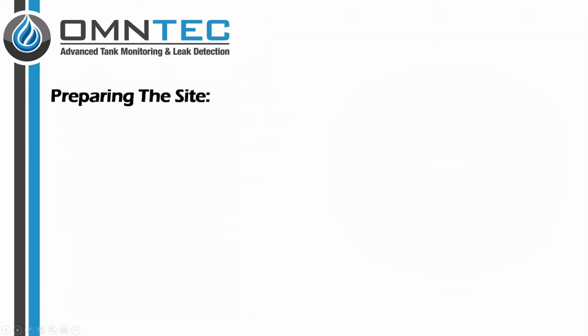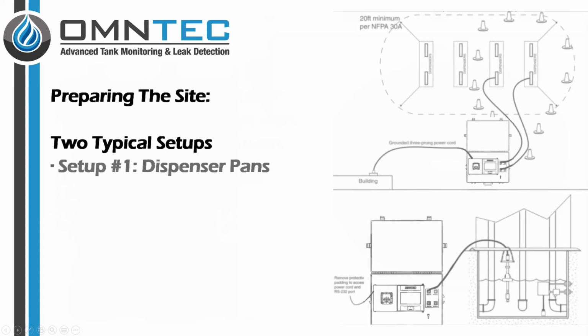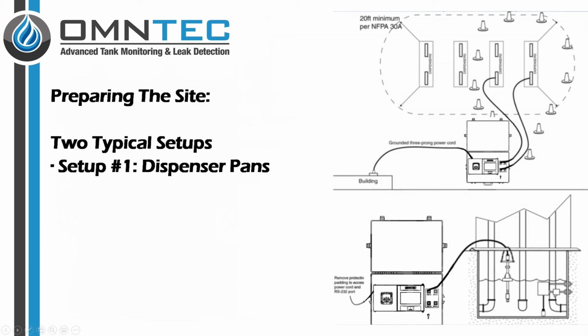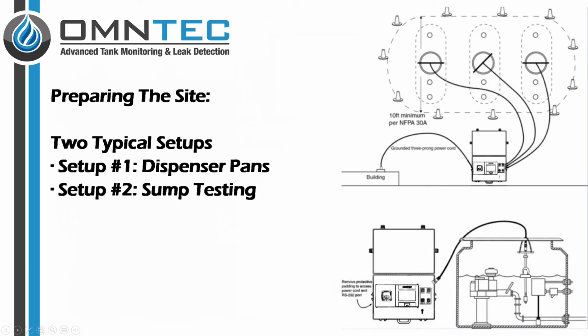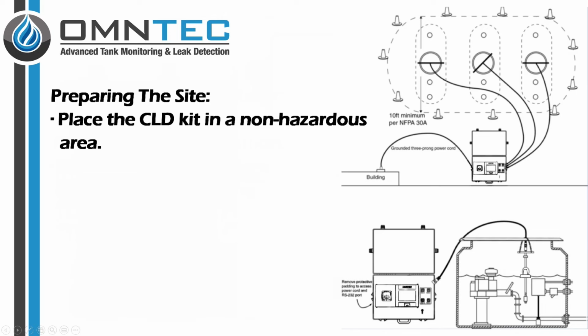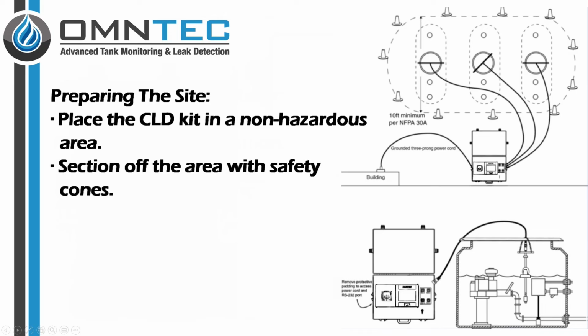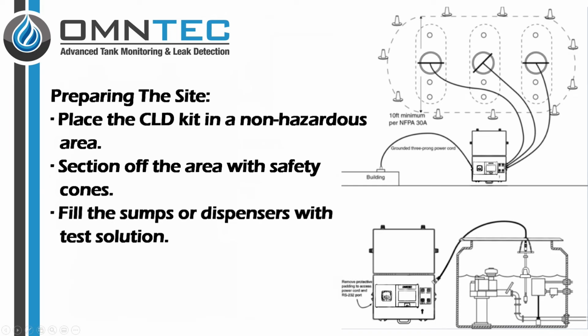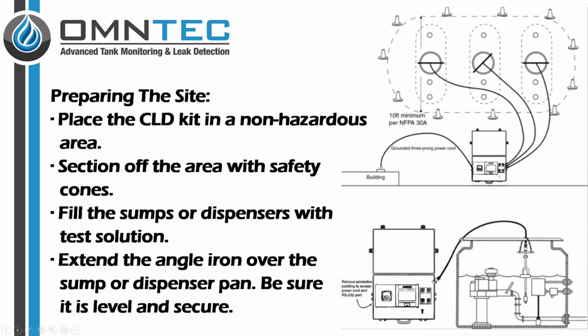Now, let's talk about preparing the site. There are 2 typical setups, one being for dispenser pans and the other for sump testing. Place the CLD kit in a non-hazardous area. Section off the work area with safety cones. Fill the sumps or dispensers with test solution. Extend an angle iron over the sump or dispenser pan. Be sure it is level and secure.